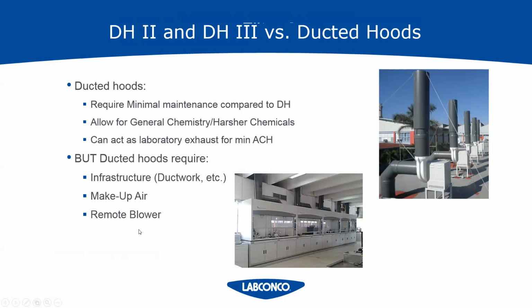So this slide shows that the ducted hoods are good for these things, but the ducted hoods do require the infrastructure, the makeup air, the remote blower. So these are things to consider. And the photos here show a really good ducted installation. You've got the hoods lined up in a row, and then the remote blowers on the rooftop. That's actually the same installation. So you see the blowers that are connected to the hood underneath them, basically.